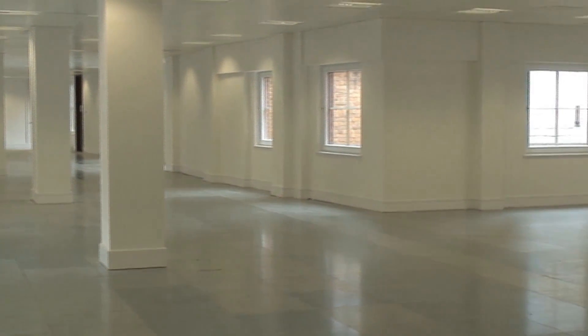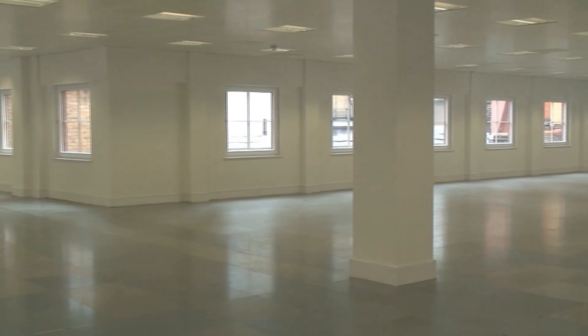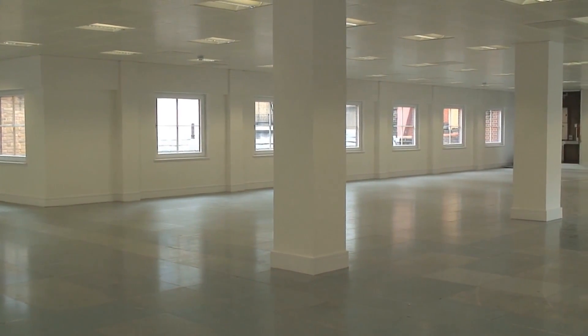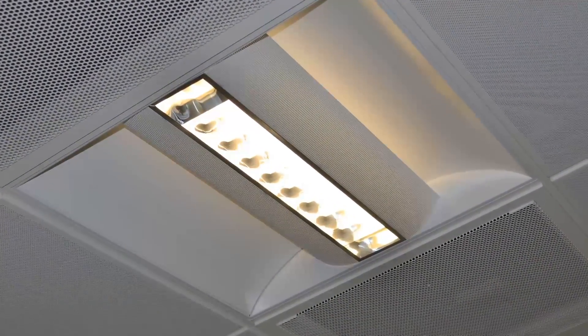The prefabricated wiring allows the office configuration to be changed very easily by unplugging and reconfiguring the system. The other advantage of the Click system is the multi-pin plugs which allow dimming as well as 240 volt power to each light fitting.